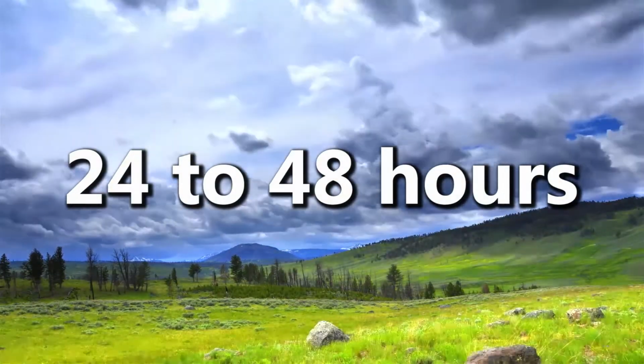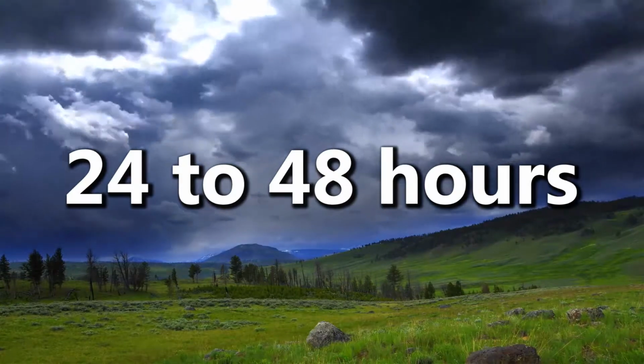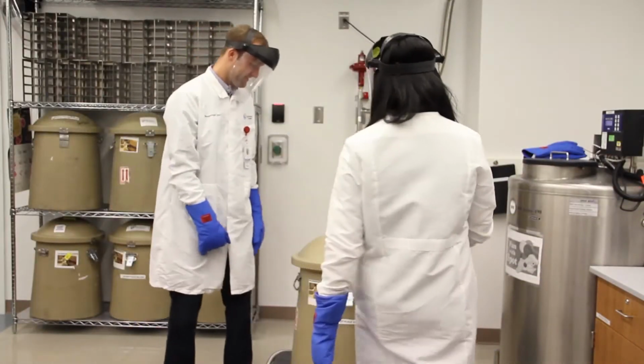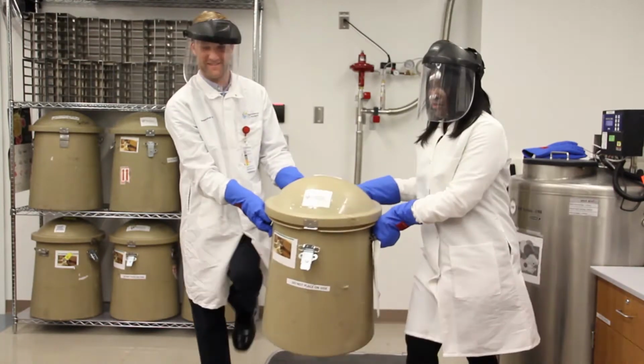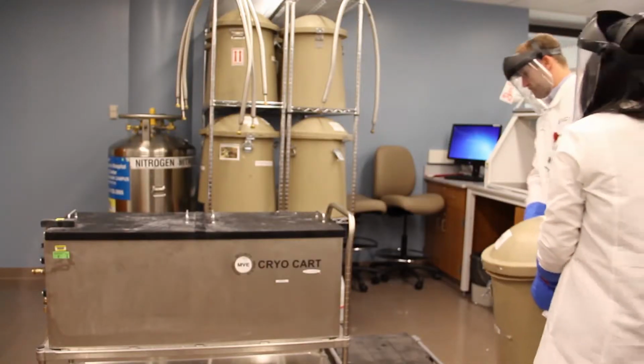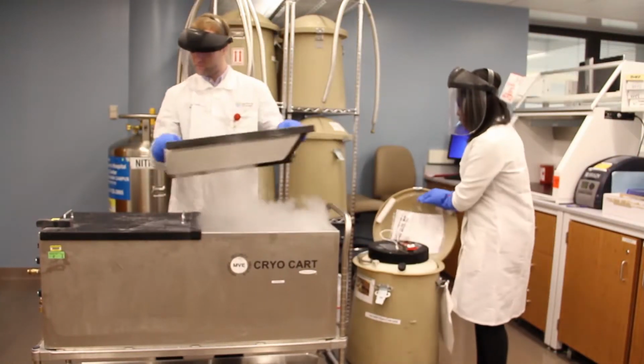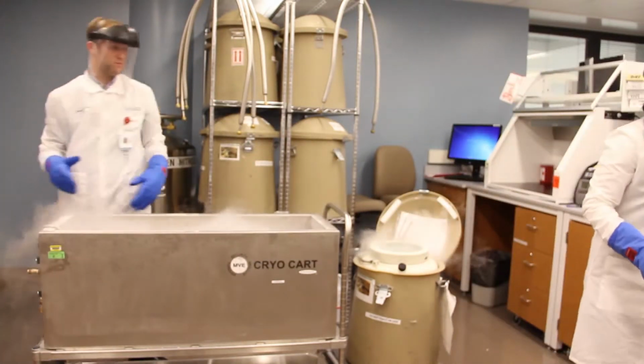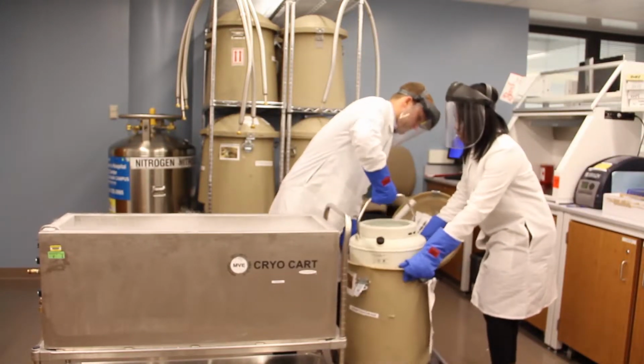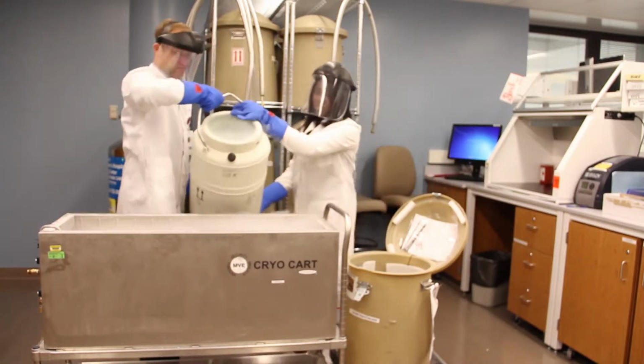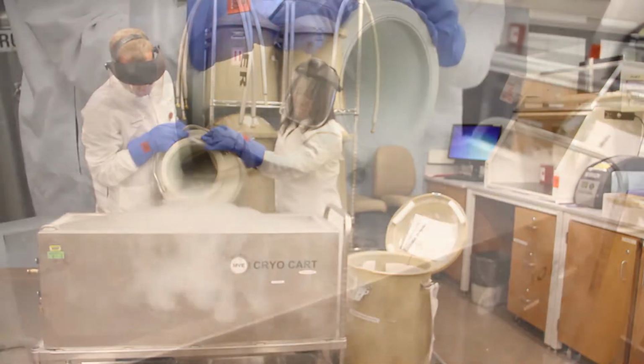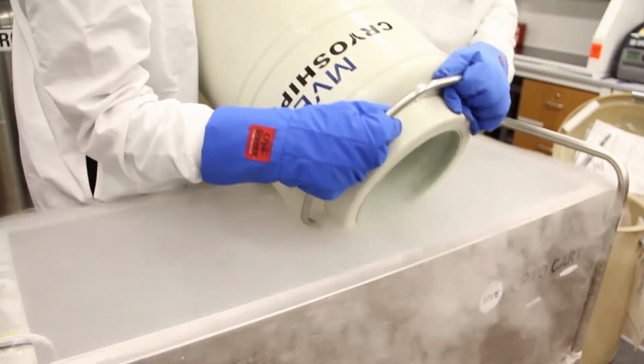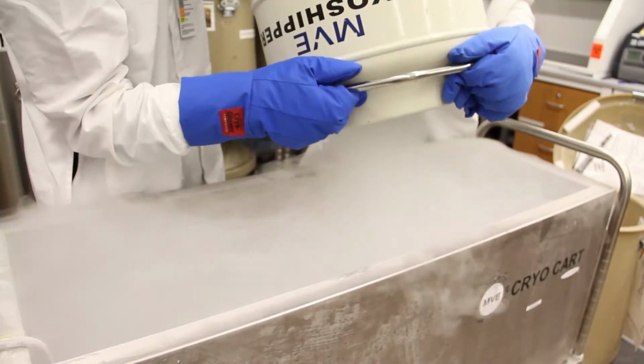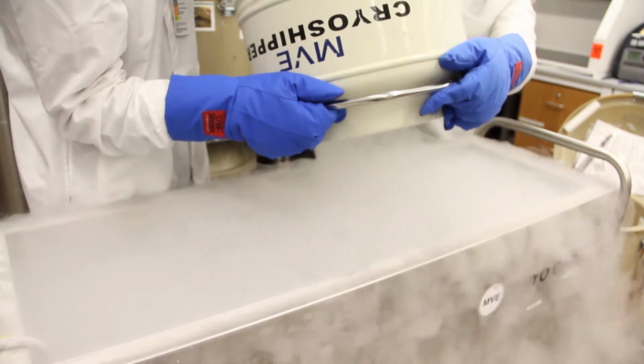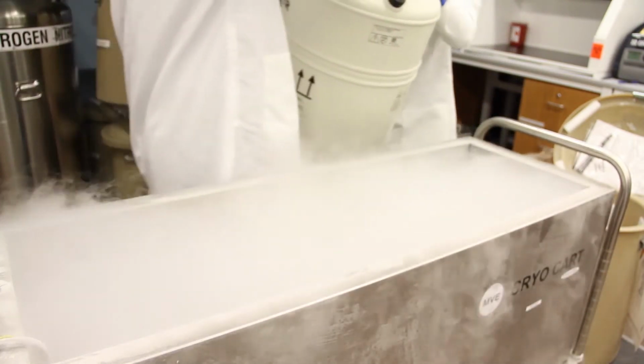Allow the cryoport to charge for 24 to 48 hours, which is ample time for the absorbent core to absorb the liquid nitrogen. When the cryoport is charged and ready to be shipped, all excess liquid nitrogen will need to be poured out into a designated waste area. Once the dewar is completely free of liquid, place the metal sample rack back into the dewar.